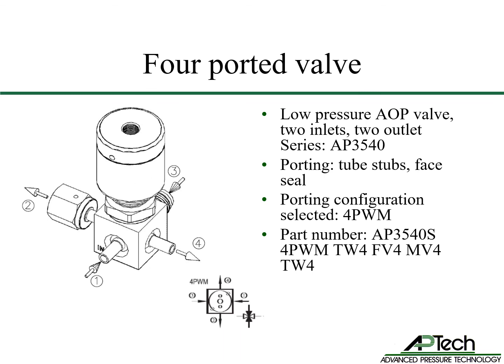Now let's configure the four-ported valve — also a 3540. Gas flows through ports number one and three, which are inlet ports. Port number one is a quarter inch tube stub, and port number three is quarter inch male face seal. Ports number two and four are outlet ports downstream of the valve seat. Port number two is quarter inch female face seal, and port number four is quarter inch tube stub. Looking at APTEC's Product Note number 443, a four-ported valve with two inlet ports and two outlet ports opposite is a 4PWM flow pattern. The ports are specified in sequential order starting with port number one, so the part number is AP3540S4PWMTW4FV4MV4TW4.